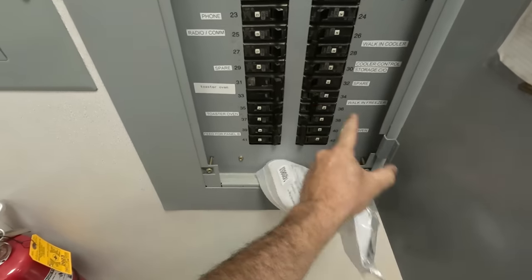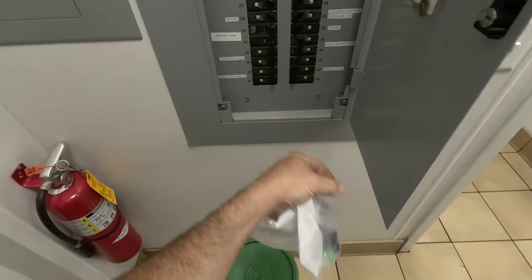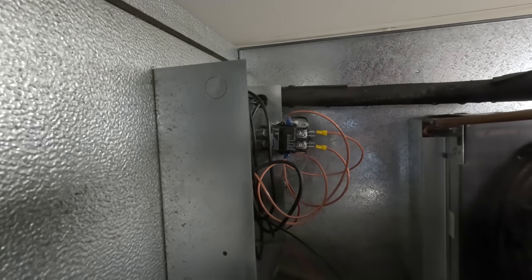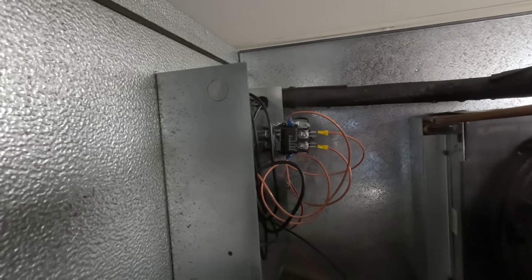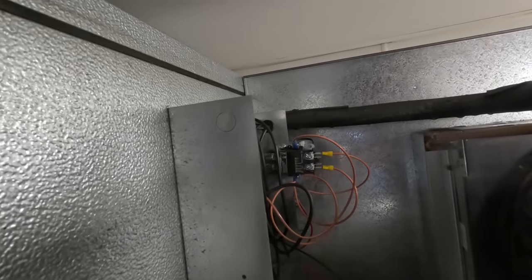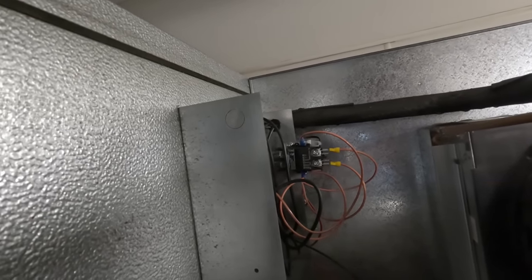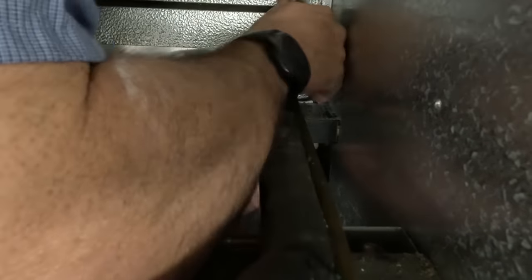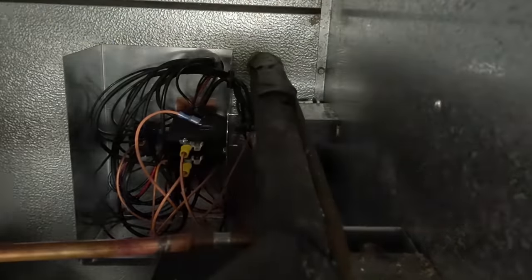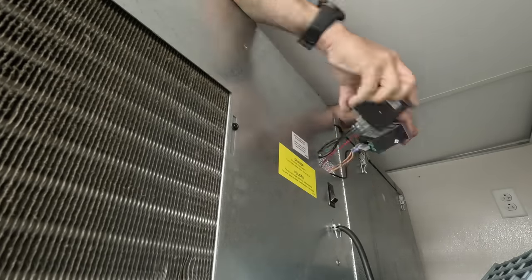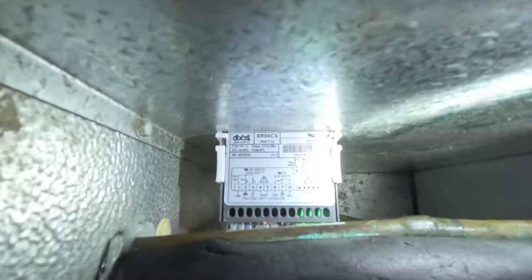Okay, walk-in freezer. Boom. There's no solenoid to pump it down, so it don't really matter whether you just turn it off or not. You can see we've got the water in the pan there. So it did melt it out like it should. What we're going to do is we're still going to utilize this contactor to kill the compressor. So the controller's going to control the contactor like it should have been done to begin with, similar to how they're doing the defrost relay there for the heaters. That way it lasts longer.